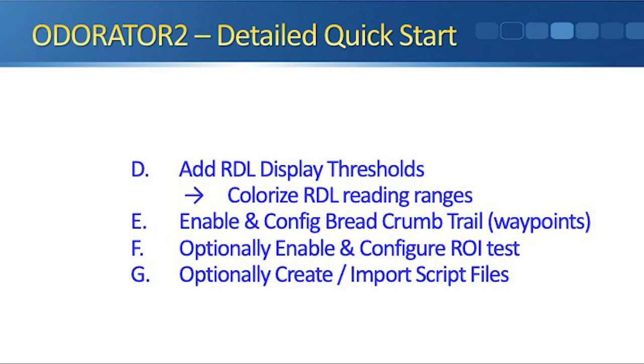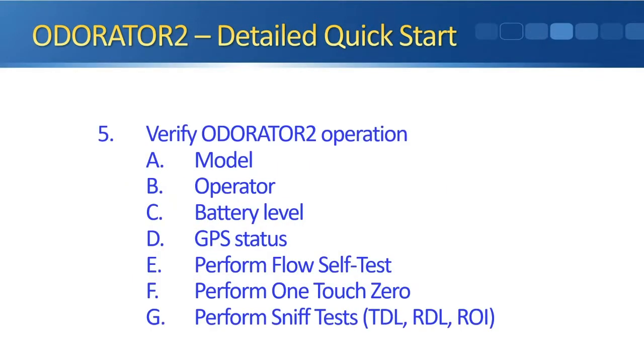Brian mentioned the optional ROI test of relative odor intensity. That's also disabled by default, but it can be enabled using the Odor Seer software. It is in addition to the RDL test. It is not a separate test. So if enabled, the sequence would go through the TDL, RDL, and then the relative odor intensity test as a full suite of tests. And then lastly, with the software, the IT manager or Odor Seer manager can create or import scripts which allow the configuration of the instrument to effectively be recorded in a file, and that file can be emailed or sent to other machines for updating, so it's easy to transfer settings between the Odor Seer software and the actual instruments out in the field.